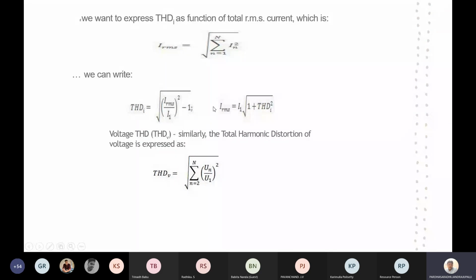So why I am saying this is, once these harmonics are injected, the losses no longer remain the same. Earlier the losses were with respect to the fundamental current, I1 square into R. Whereas once harmonics are present, these are transformed to IRMS, and they become I1 square into (1 plus THD square) times R. Similarly, it is true in the case of voltage harmonics also. We need to calculate both voltage as well as current harmonics. In the case of voltage, it will be the square root of sigma n equal to 2 to n, (Vn by V1) whole square.